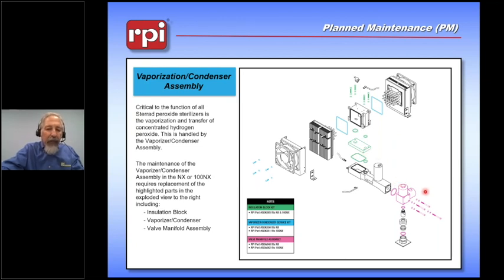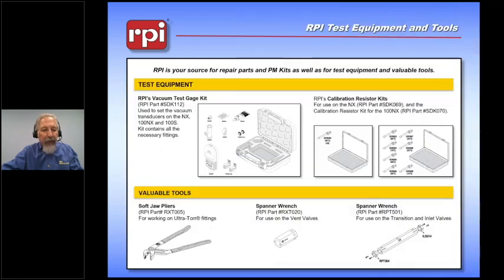So we have a kit available that includes all of these parts that are highlighted in color. We also include a new vaporizer manifold assembly that includes an inlet valve and a transition valve, since they are the last steps that the hydrogen peroxide sees before it's sent into the chamber, and you can build up salt deposits within this assembly as well, and we want you to be able to replace it without needing to clean it. So this vaporizer condenser kit is available for the NX, and there's also a version for the 100NX. The 100S does not do this process. It has an injector assembly, and it also has a separate kit as well.